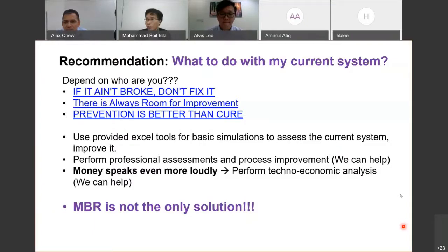If you operate with a lot of cleanings and a lot of fouling, then the lifetime will probably be less than 3 years. But if you operate it very well, there are MBRs that have been running for 20 years without replacement of the membrane. Okay, I think the answer is quite clear.